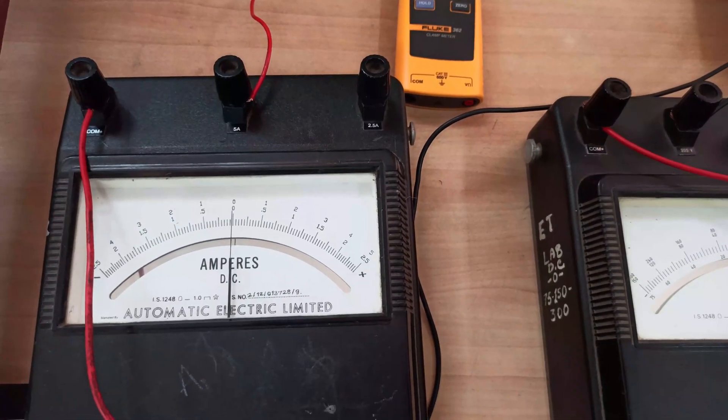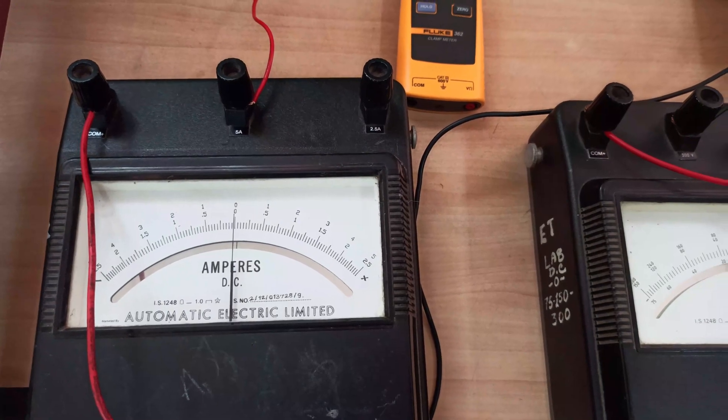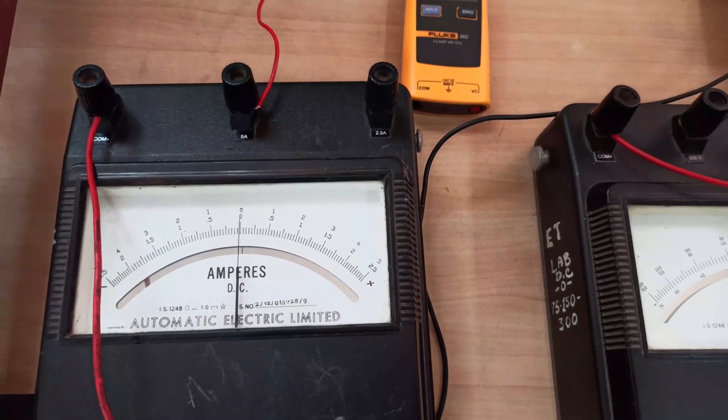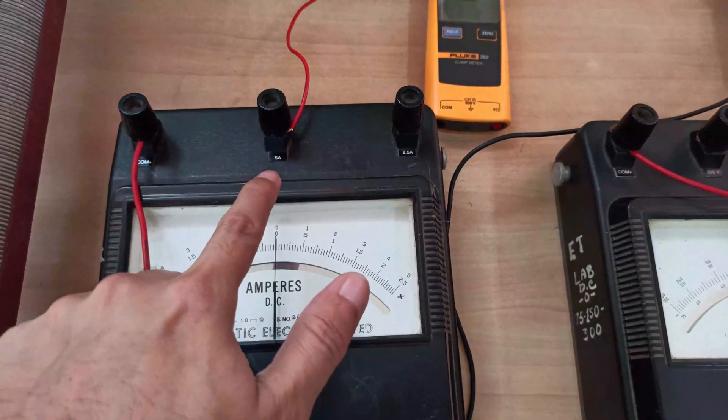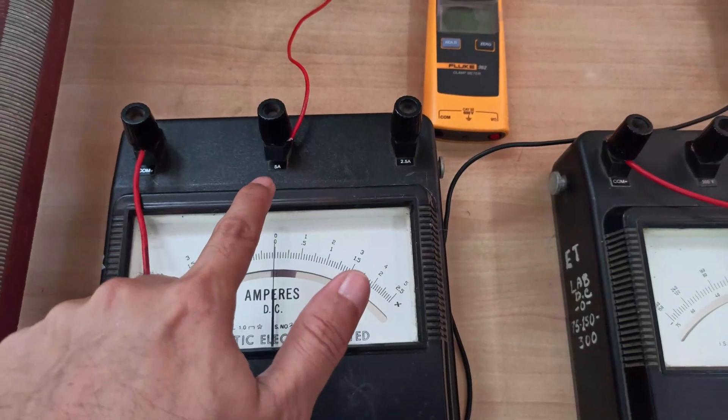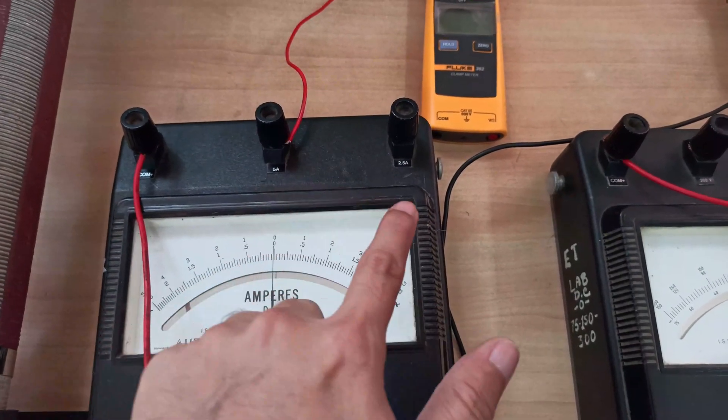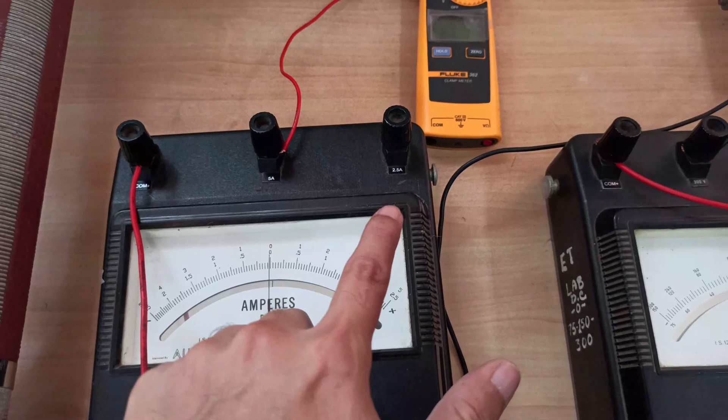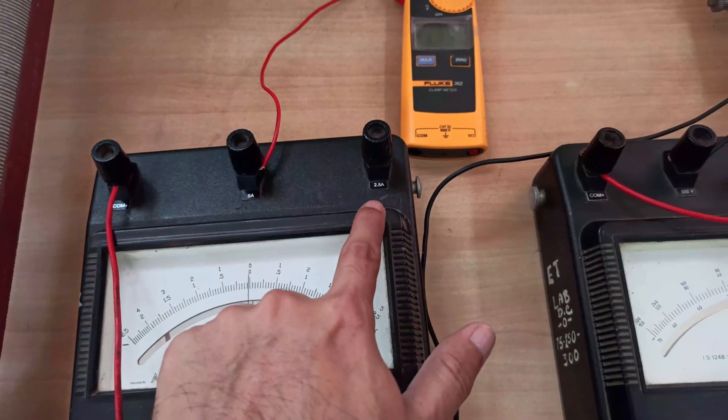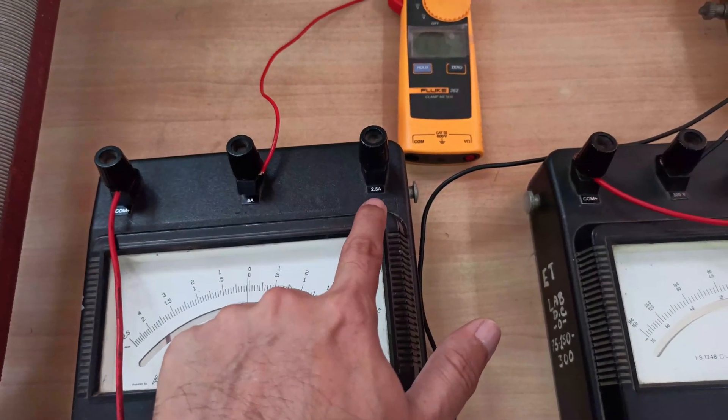For example, if you calculate that maximum current that is going to flow in your circuit is around 3 ampere, you will be selecting this 5 ampere scale. And if you are very sure that current will be within 0 to 2 ampere, then you use this 2.5 ampere scale.